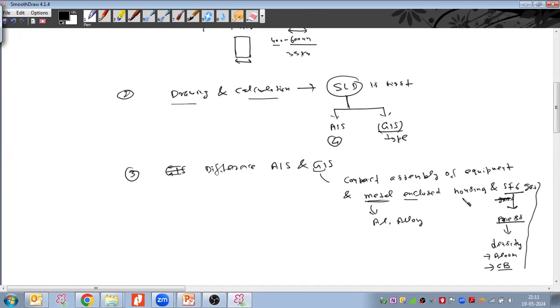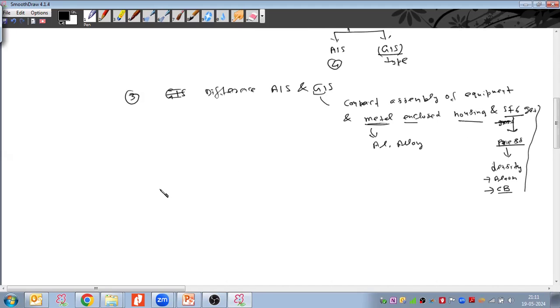And this metal enclosed housing also we have taken in the GIS. We discussed yesterday that this metal enclosed housing is not a common enclosure for all. This metal enclosed housing is internally divided, or we can say subdivided, into separate gas proof compartments with the help of gas barrier insulators. This is what we discussed yesterday, gas barrier insulators.